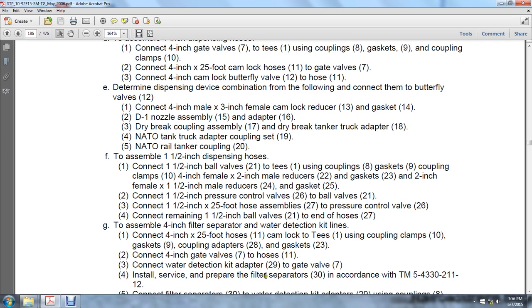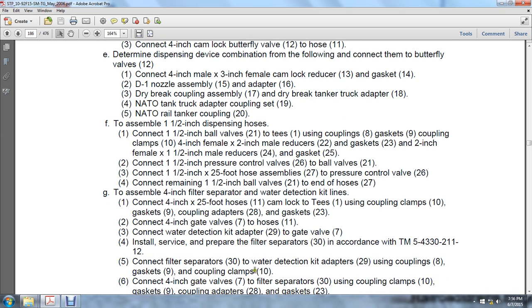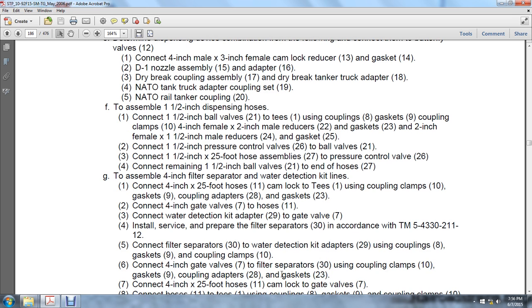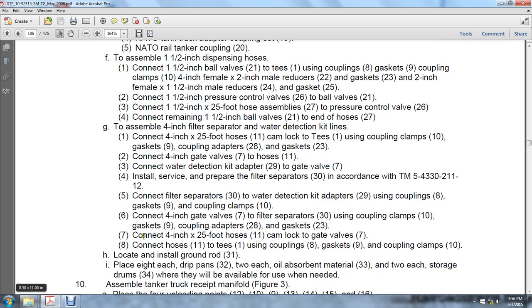Install and prepare the filter separators (30) in accordance with TM 5-4330-211-12. Connect the filter separator (30) to the water detection kit adapters using the couplings, gaskets, and coupling clamps. Connect the 4-inch gate valves (7) to the filter separators using the coupling clamps, gaskets, couplings, and adapters. Connect the 4-inch 25-foot cam lock hose (11) to the gate valves, and connect the hose (11) to the tees using couplings (8), gaskets (9), and coupling clamps (10).